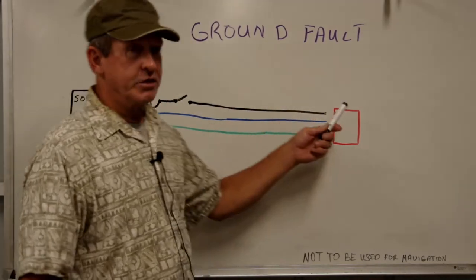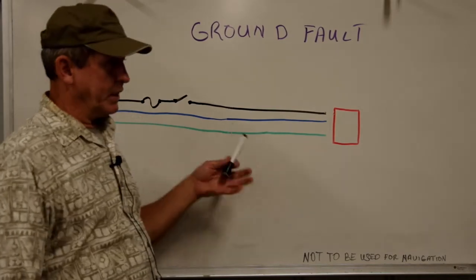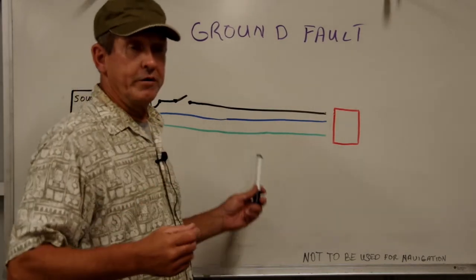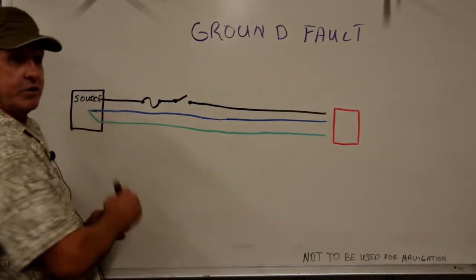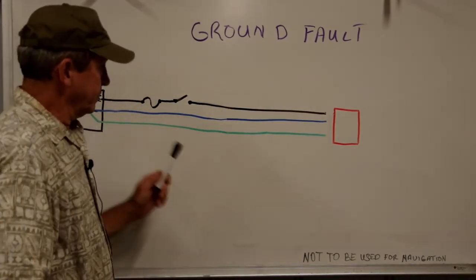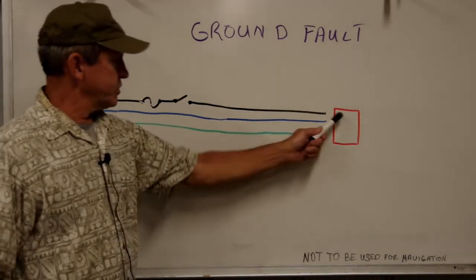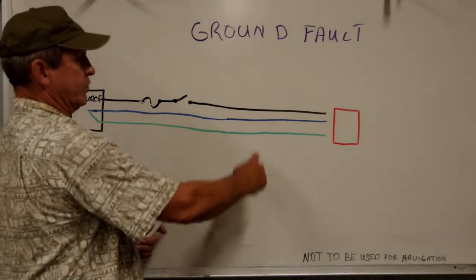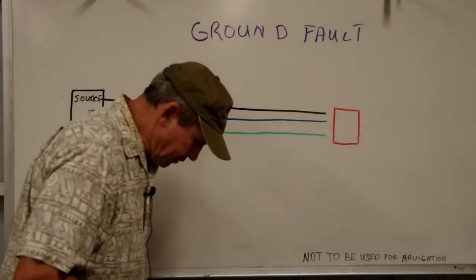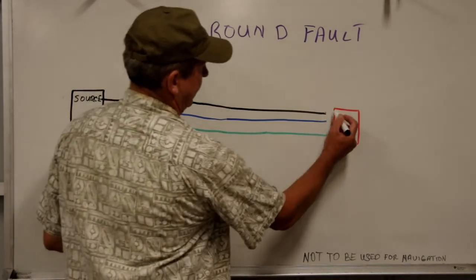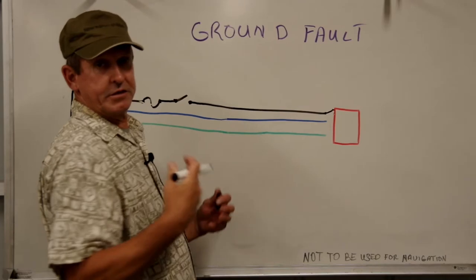I've drawn a simple AC circuit — let's call this our 120-volt AC circuit. We have a source of power, our appliance, circuit protection, a switch, a line, a neutral, and an AC safety ground. If our line happened to come in contact with the case or chassis of this appliance, our line has shorted to the chassis of our appliance.